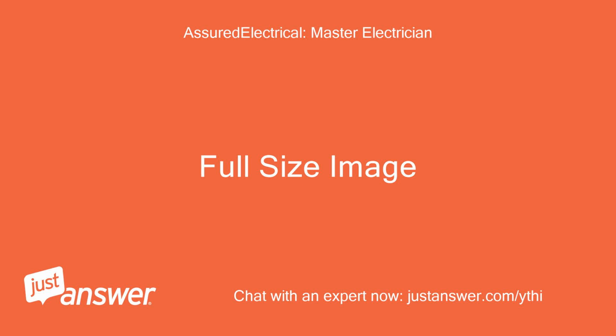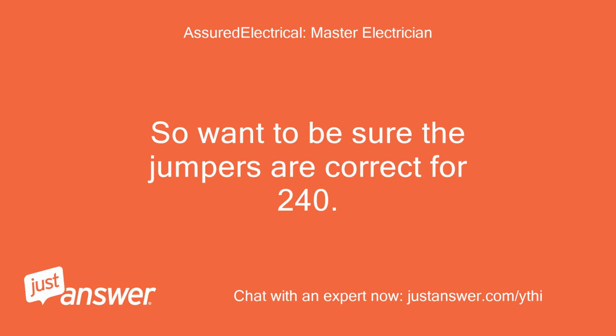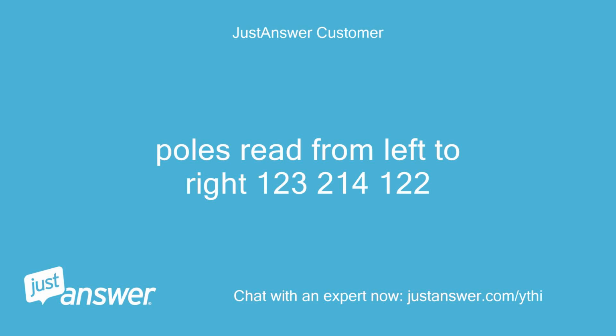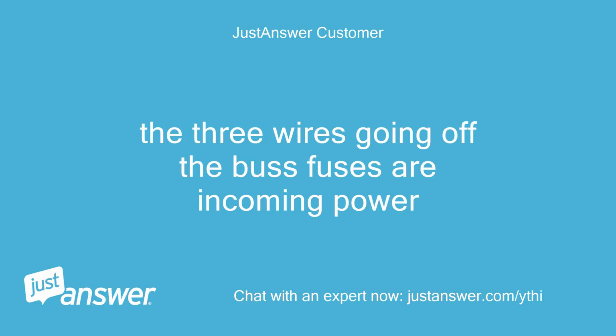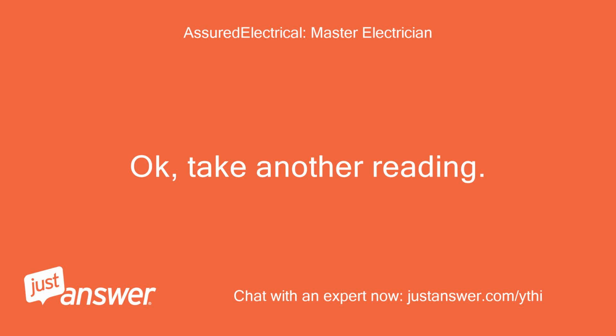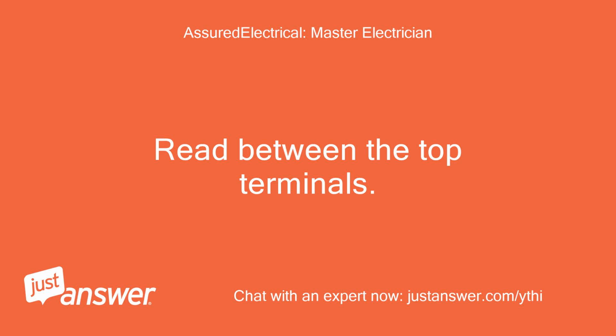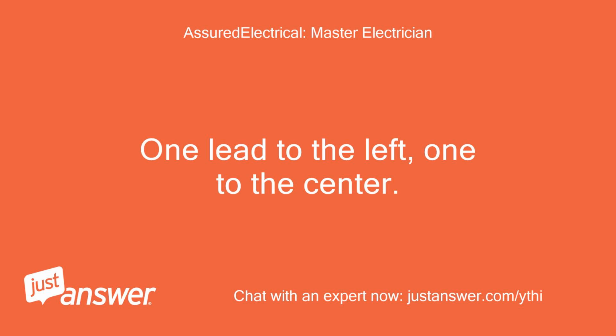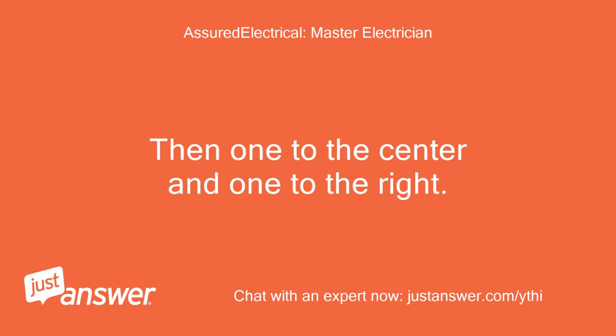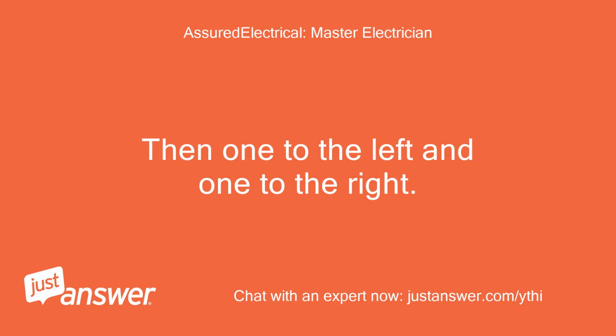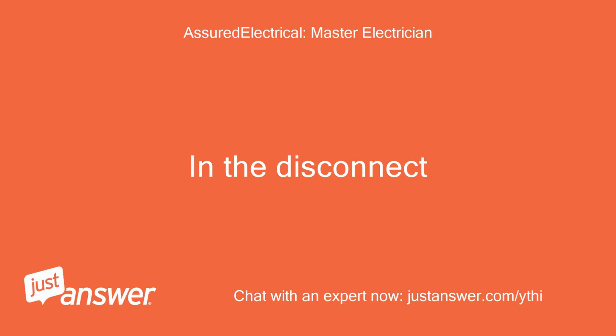So want to be sure the jumpers are correct for 240. Poles read from left to right 123, 214, 122. The 3 wires going off the bus fuses are incoming power. Okay, take another reading. Read between the top terminals. 1 lead to the left, 1 to the center. Then 1 to the center and 1 to the right. Then 1 to the left and 1 to the right. In the disconnect.